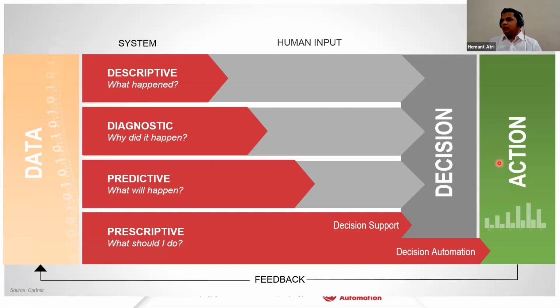So from the analytics perspective, this is the precursor of the system - these are the current systems which actually indicate what happened. What do I mean by that? If a pump is running with basic automation provided, when the pump gets tripped, the operator gets an alarm on the SCADA that the pump has tripped. And what does that mean? It means it's going to need a certain amount of human input and decision-making to take action to bring the pump or system back to operation.